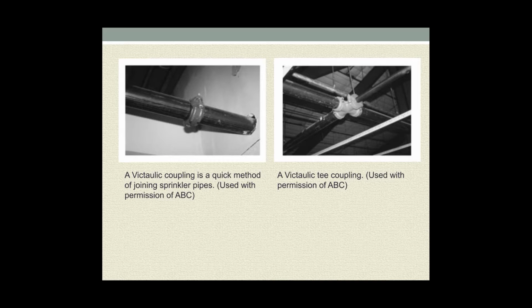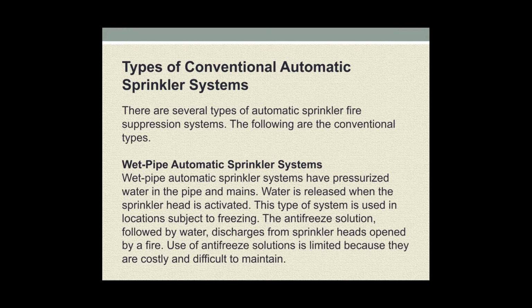Next is types of conventional automatic sprinkler system. There are several types of automatic sprinkler fire suppression system. The following are the conventional types. Wet pipe automatic sprinkler system. Wet pipe automatic sprinkler systems have pressured water in the pipe and mains. Water is released when the sprinkler head is activated. This type of system is used in locations not subject to freezing. The antifreeze solution mixed with water discharges when sprinkler heads open by a fire. Use of antifreeze solution is limited because it is costly and difficult to maintain.